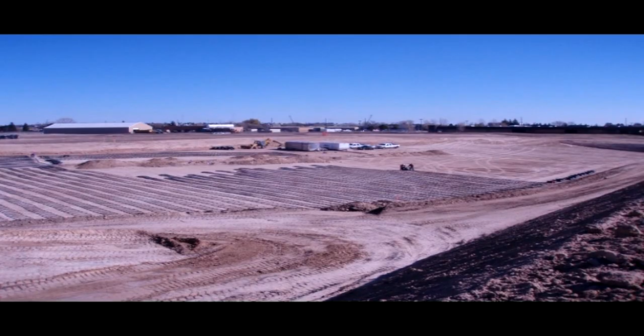Joint Forces Readiness Center up in Cheyenne at Warren Air Force Base. Again, 240,000 feet of 1,000-foot slinky coils. And we'll take a look at this. We dug a hole that was literally almost 12 acres in area, basically 10 foot deep. You can see each one of these represents 1,000 linear foot of pipe all coiled up that then we would come back in and backfill back up to about that level when we're done. They seed it and put a parking lot over it and it's done. And here again, here's our equipment in action, moving a lot of dirt. We've even got a B-52 up in the sky there I was able to catch, unbeknownst to me till I looked at the picture.